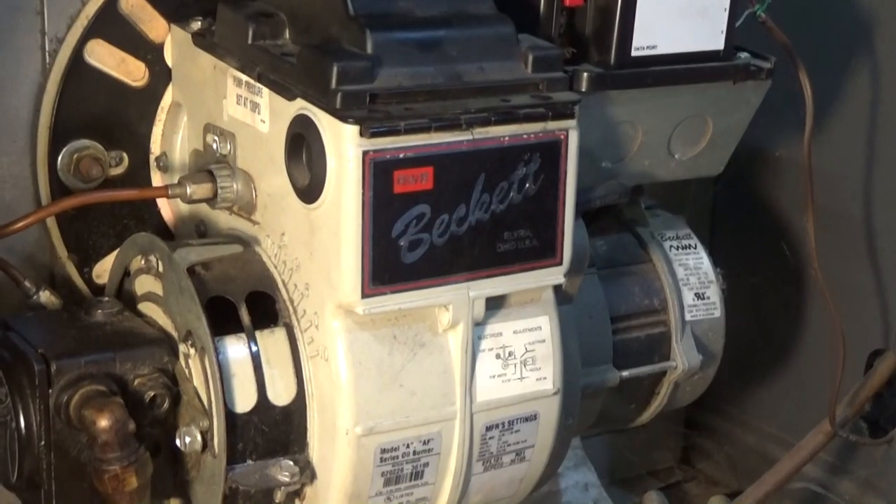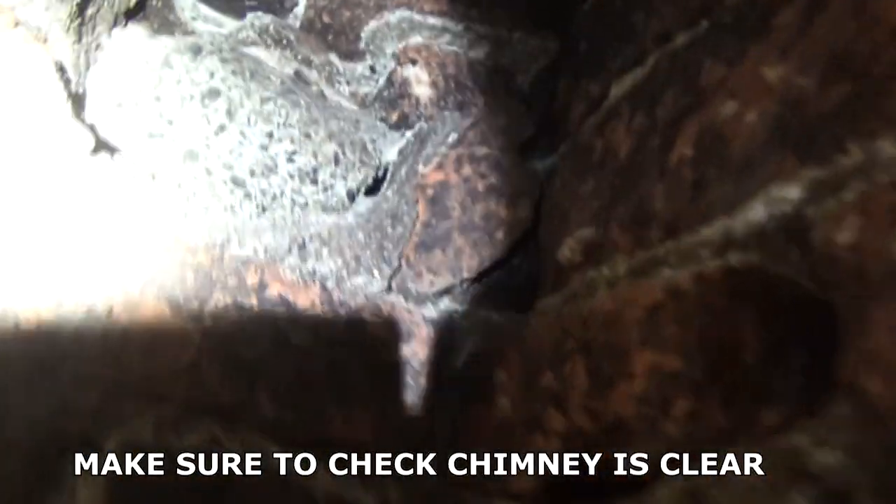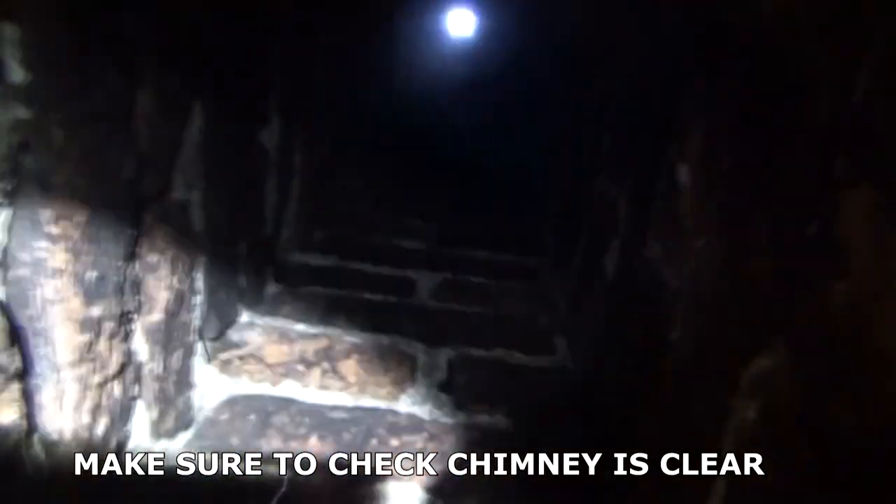Alright Ray, turn her back on — we'll see how nice she fires. Fired right up, burning. This is a hot air furnace. Last time we looked at the chimney, the flues had crashed down in there and we had to take them out — Michael patched it, or rather ripped the patch out and we'll repatch it. I'm going to vacuum it. Looking inside this old chimney — we're clear. There's the exhaust and there's nothing in there, which means it's burning clean.